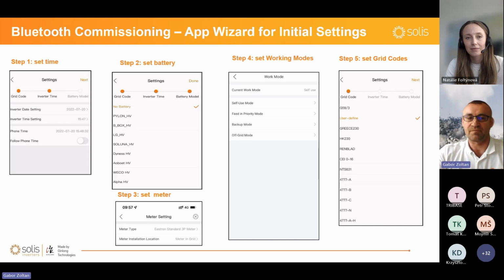First of all, you set the time. It's really easy. Just click on follow the phone time. Your smartphone time will be given to the inverter as a basic time. Step 2, set the battery. Solis has approximately 60 different battery brands and types which are allowed to be used. When you choose your inverter, you can download the battery list which is allowed to be used with this exact inverter. And you can find the correct battery that you want to use. So during the setting, you can see some examples like Pylon, Soluna, LG, Weco, or other. You can find the correct one, just click on it and it's set.